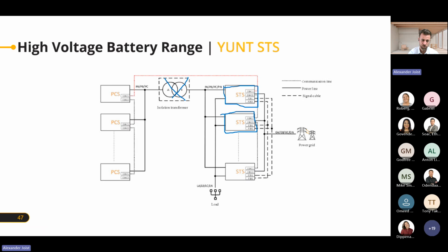We can do 2 without a transformer and still with 10 milliseconds. If we add more, it's not synchron anymore. The changeover is not synchron. So as soon as we do more switching with the STS, we're going to need the transformer for the harmonics, and the switching time will be higher than 10 milliseconds, because these multiple products can't be switching in that very short time, super fast, under 10 milliseconds, doing exactly the same thing and then synchronizing the grid at exactly the same time. There's just a communication delay, and that will definitely not be 10 milliseconds anymore. It will be a couple of seconds, maybe 10, 20 seconds or something like that, until they're all closed and everything communicates together and builds up a grid again. But then it can generally build up a grid.